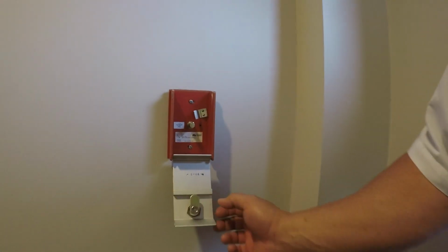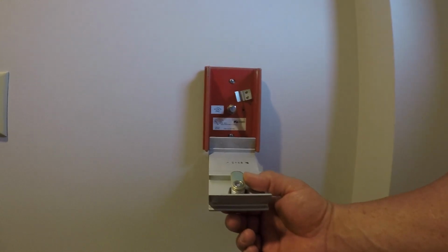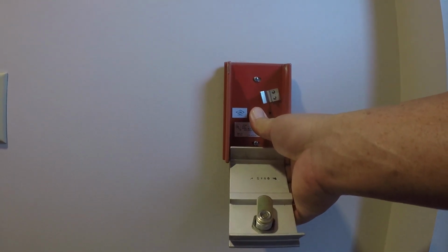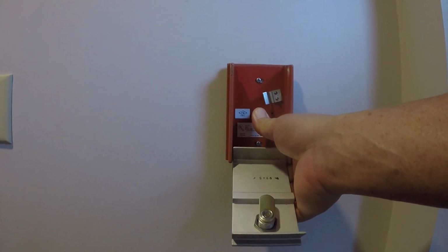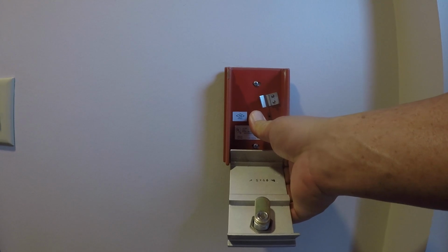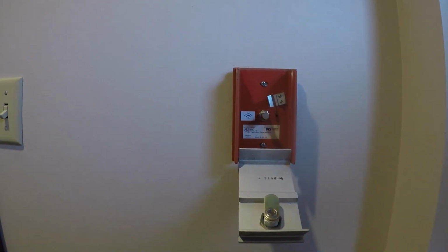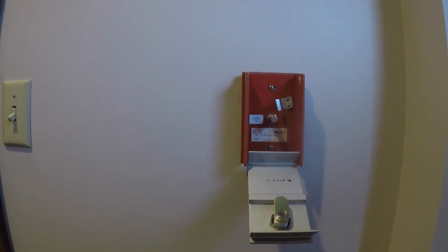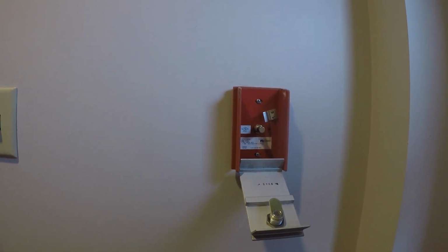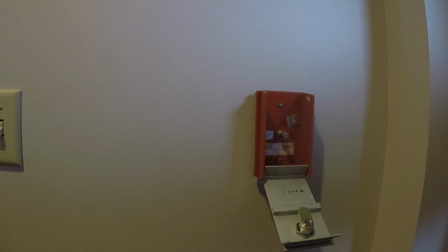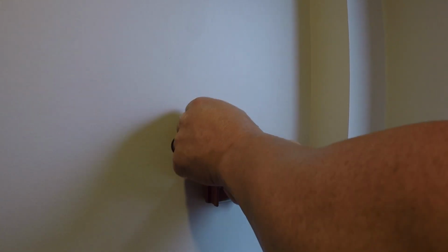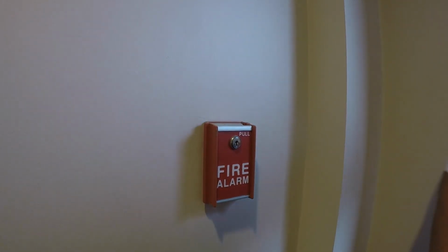So the way this works is, this is just like any door latch. It fits in behind this and it pushes this button in. So once that button is pushed in, the system is reset, and then you go to your alarm panel and you reset it from there. When I release this, it's going to sound off again. So we typically do not carry keys. You'll find these in the Knox box or again with the property representatives. So that is reset.